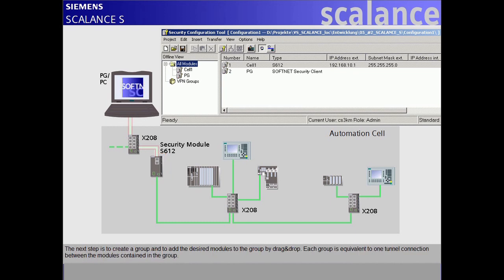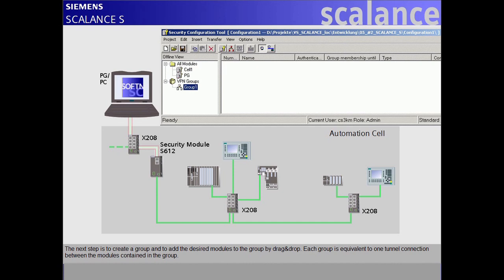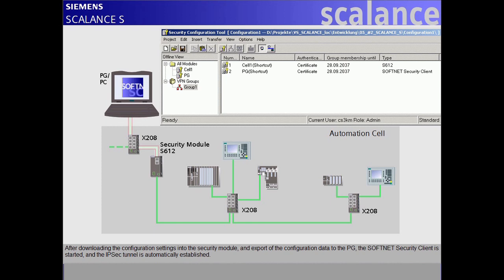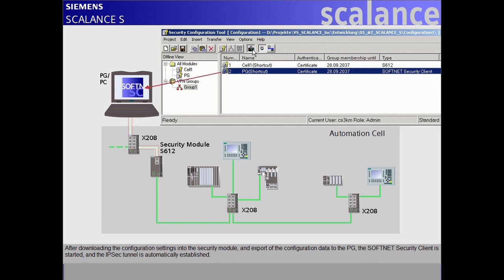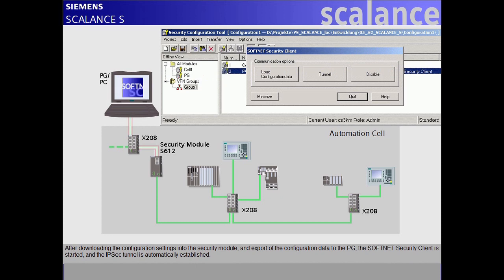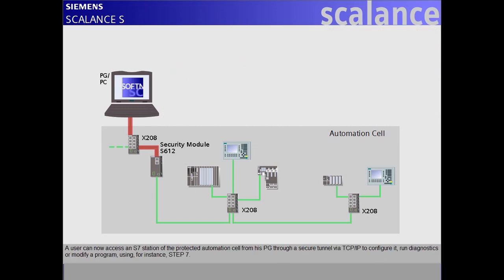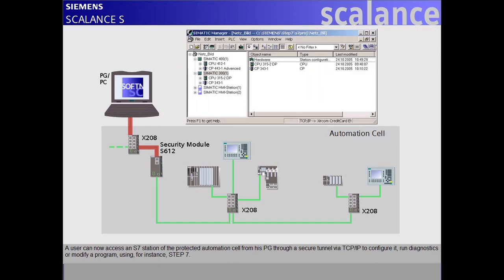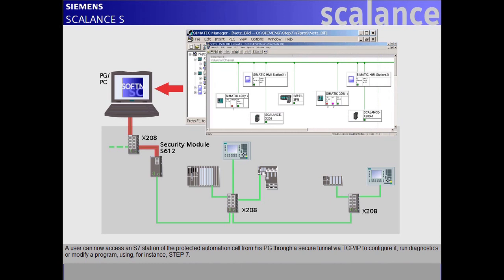The next step is to create a group and to add the desired modules to the group by drag and drop. Each group is equivalent to one tunnel connection between the modules contained in the group. After downloading the configuration settings into the security module and exporting the configuration data to the PG, the SoftNet Security Client is started and the IPsec tunnel is automatically established. A user can now access an S7 station of the protected automation cell from his PG through a secure tunnel via TCP/IP to configure it, run diagnostics, or modify a program using, for instance, Step 7.